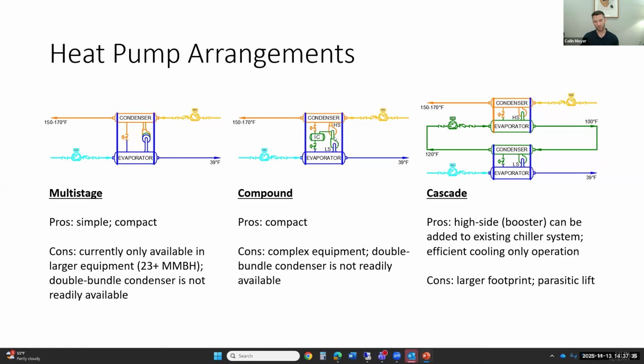The way that there are two compressors in series, there's actually a really good opportunity to divert the discharge from the low pressure compressor into a heat rejection bundle. So this is something that's still emerging on the market to follow in terms of deploying these larger water-to-water units. Because if we could get equipment that could do heating duty in the winter, but also do efficient cooling in the summer, all the equipment can kind of be consolidated, and it'll help with payback for decarbonization projects.